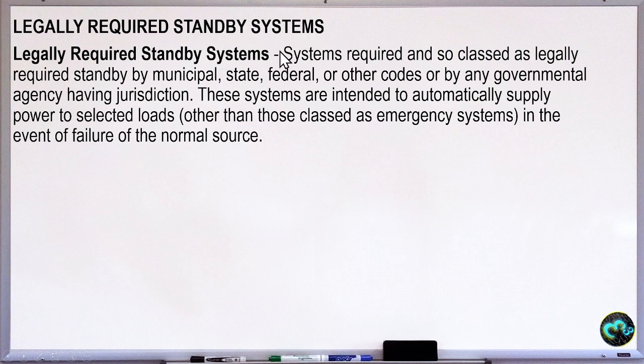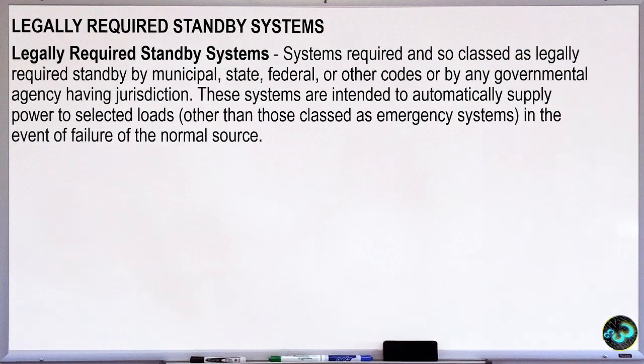Legally required standby system. So legally required standby systems are systems required and so classed as legally required by municipal, state, federal or other codes, or by any governmental agency having jurisdiction. These systems are intended to automatically supply power to selected loads other than those classed as emergency systems in the event of failure of the normal source. For example, in a certain municipality, they have their own backup generator that could supply a portion of their constituents, so that is considered as legally required standby system as long as it is approved by any governmental agency having jurisdiction.